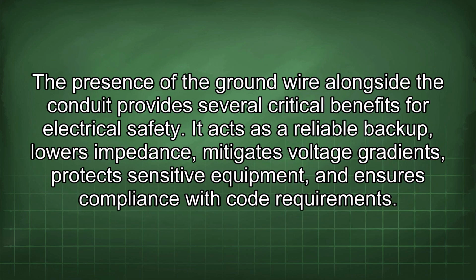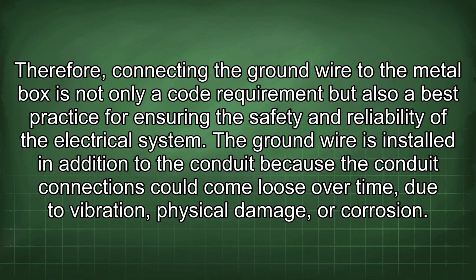The presence of the ground wire alongside the conduit provides several critical benefits for electrical safety. It acts as a reliable backup, lowers impedance, mitigates voltage gradients, protects sensitive equipment, and ensures compliance with code requirements. Therefore, connecting the ground wire to the metal box is not only a code requirement but also a best practice for ensuring the safety and reliability of the electrical system.